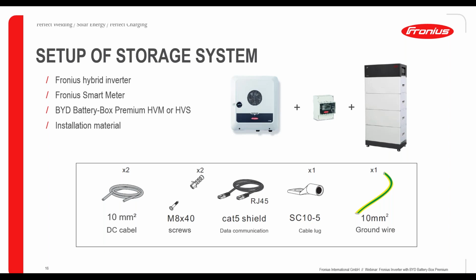Furthermore, for the ground wire, you need cable lugs. In this case, you can use a standard cable lug for fixing the ground wire, the protective earth, on the battery box itself. Please note, however, BYD says you need an extra protective earth cable with extra potential to earth. So it is not enough to just connect the ground wire to the Fronius inverter, but you really need to bring it to an extra potential in the electric circuit, for example, in the electric cabinet at the house connection. So please make sure to connect this ground wire correctly.